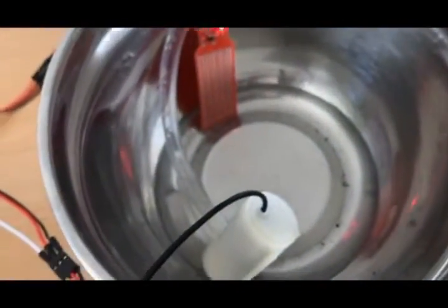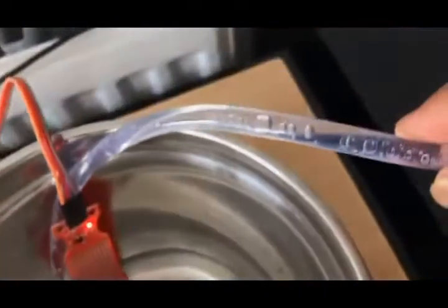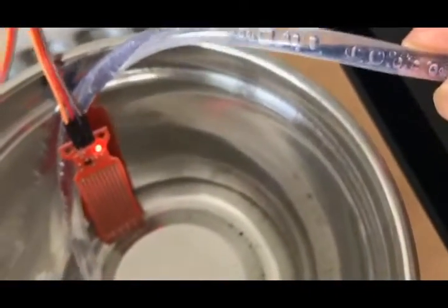And if you look at the pipe all over here, there's a lot of air bubbles. That isn't good for the pump. So you need to keep it completely submerged underwater.